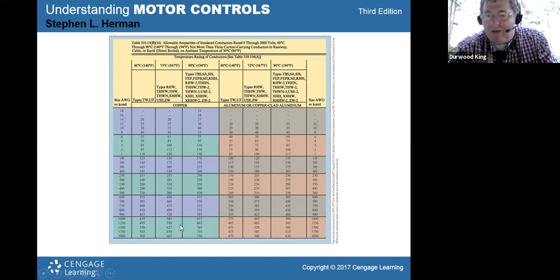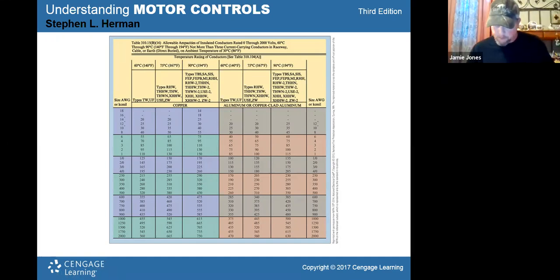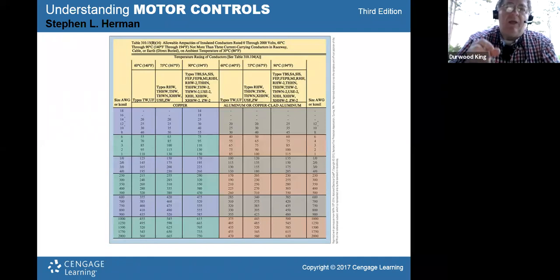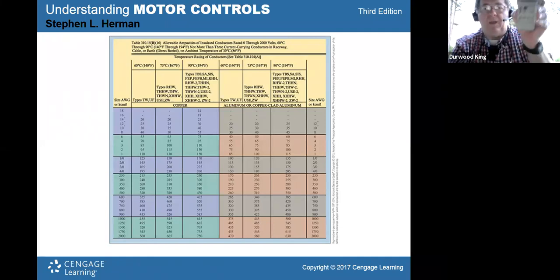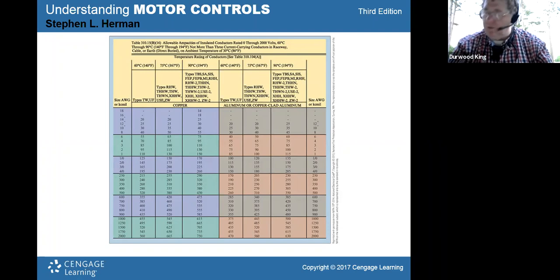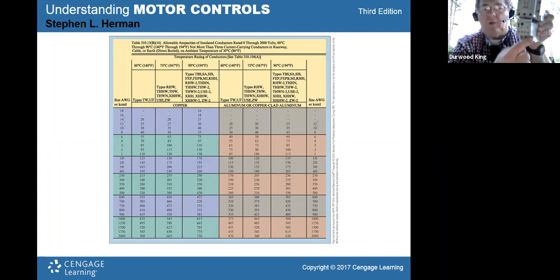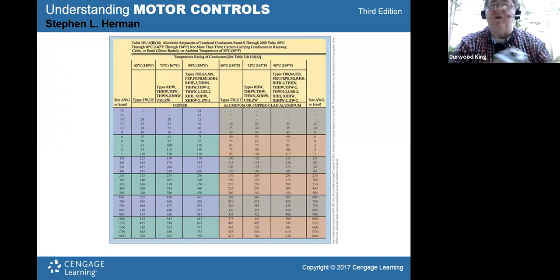Is everybody okay with how we figured that? Yeah. Now, the wire size is the minimum wire size. How about the overload setting? You've got an overload right here. How do you know what to set the overload to? It has a screwdriver adjustment that you can turn to set the trip rating on the starter. So how do we know what to set that to? Believe it or not, it's the same number. It's that 125% that we had. So the 518 amps that you just calculated is what the overload would be set to. It's 125% of your full load rating.